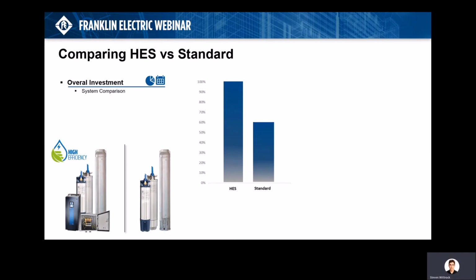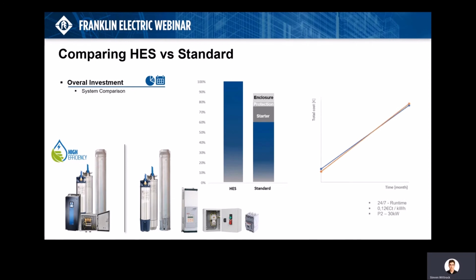In fact, when using a standard system, you need to add several components to achieve similar functionality and features as you can have with a high efficiency system. So most of the time you will need a starter, whether this is an electronic soft starter or a typical star delta starter to run your induction motor. Next, you need certain protection devices such as an overload circuit breaker, and finally you have to get everything installed in an additional enclosure or housing. If we then compare both types of systems, you see that the gap is even smaller. On top of everything, the high efficiency system lets you reduce your operational cost, which leads to payback times within 12 months, based on your duty cycles and energy prices. And beyond that point, you save pure money.